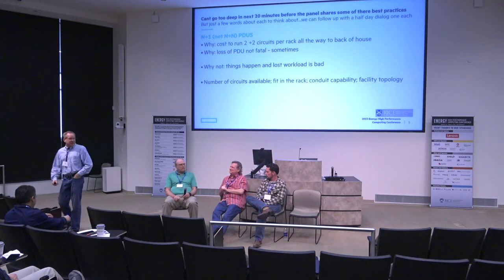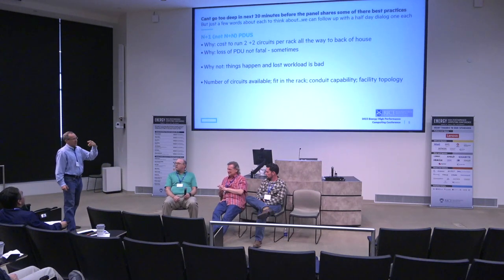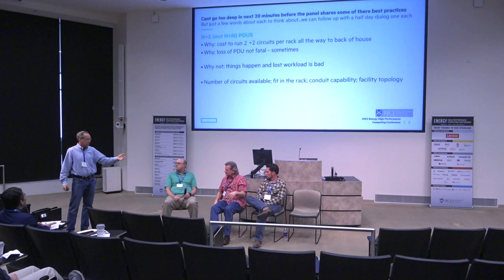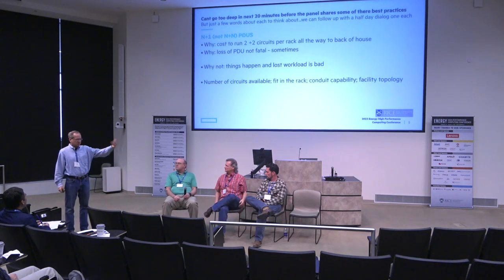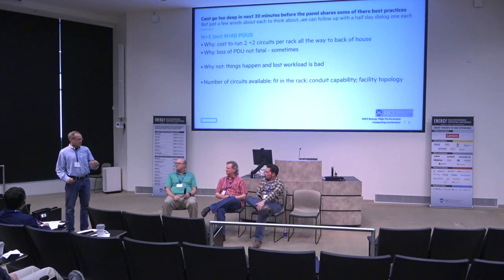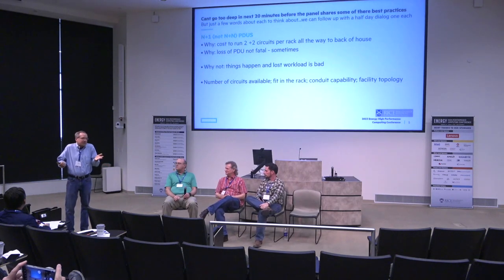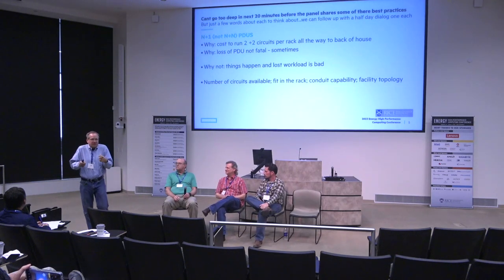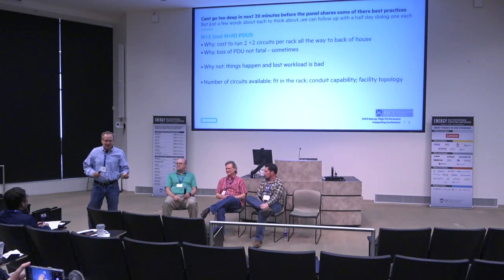That's a good segue into the next topic. You talked about power failures, and you talked about your next generation, the 2025 system going above 100 kilowatts a rack. But in the U.S., we derate, it just is what it is. 150-amp circuits, really 120. And unfortunately, the bus plug, the IEC bus plug, in Europe they call it 125-amp. I don't know why we call it 100-amp in the U.S., it's the same darn thing.